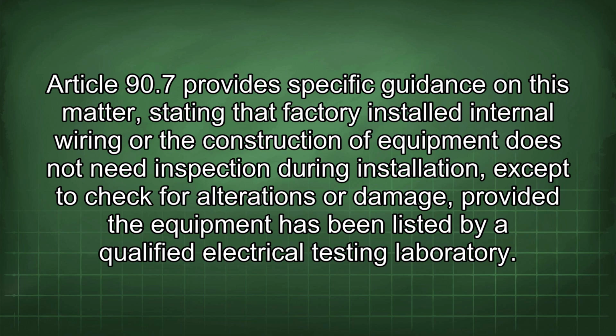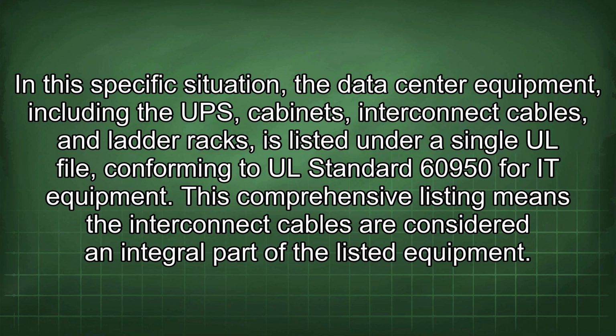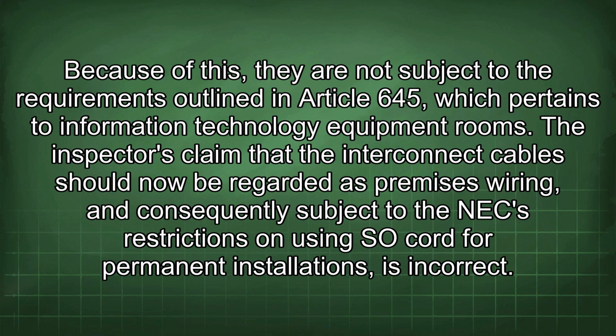electrical testing laboratory. In this specific situation, the data center equipment, including the UPS cabinets, interconnect cables, and ladder racks, is listed under a single UL file, conforming to UL standard 60950 for IT equipment. This comprehensive listing means the interconnect cables are considered an integral part of the listed equipment. Because of this, they are not subject to the requirements outlined in Article 645, which pertains to information technology equipment rooms. The inspectors claim that the interconnect cable should now be regarded as premises wiring, and consequently subject to the NEC restrictions on using SO cord for permanent installations, is incorrect.